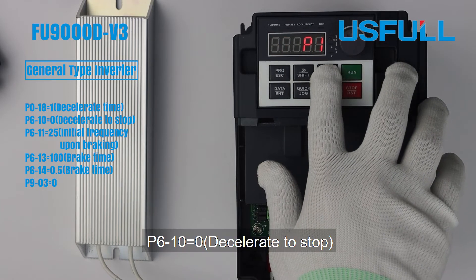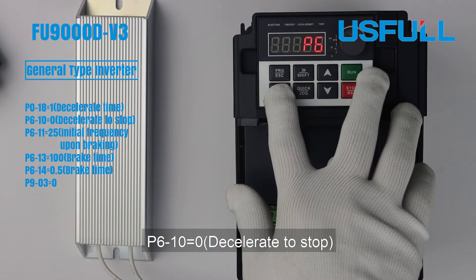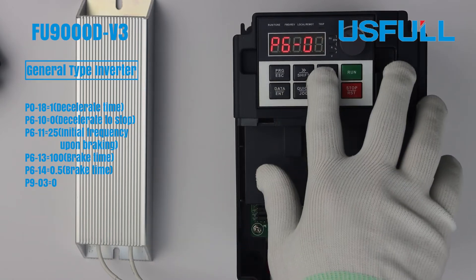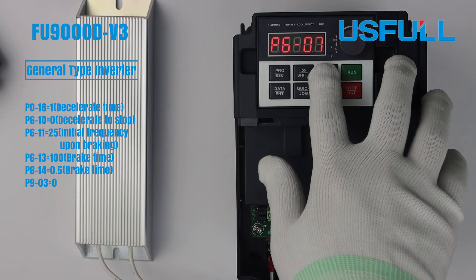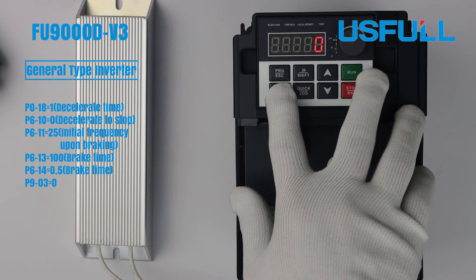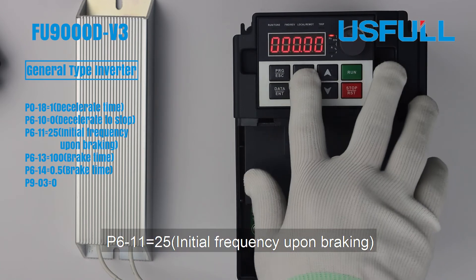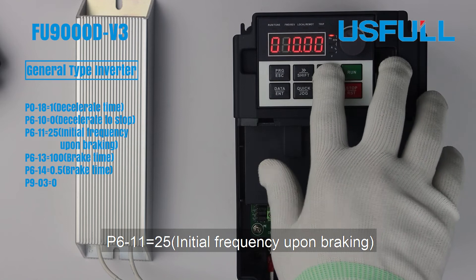Set P6-10 to 0, decelerate to stop. Set P6-11 to 25, initial frequency upon braking.